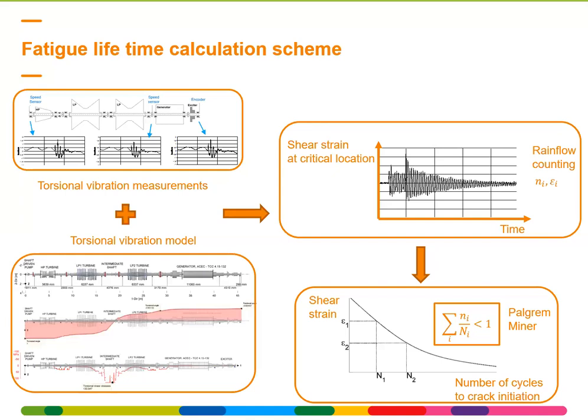The top left shows the schematic view of the shaft line with three sensors. So this is a shaft line here in Belgium where we have sensors at both shaft ends and also one sensor in between the low pressure steam turbine and the generator. Once these torsional vibration measurements are post-processed, you need some way to interpret them. And the only way to do that is by using a torsional vibration model. This is shown on the figure below. The torsional vibration model is typically used, as you can see here, to subdivide the rotor into several different segments, up to 300, for instance.